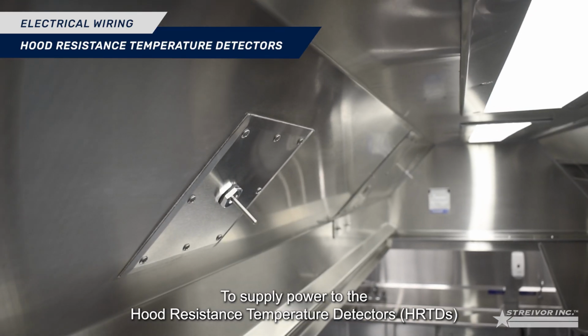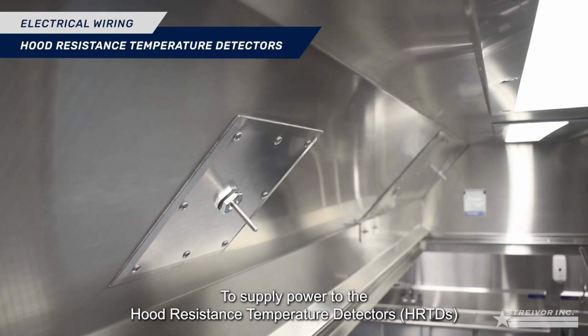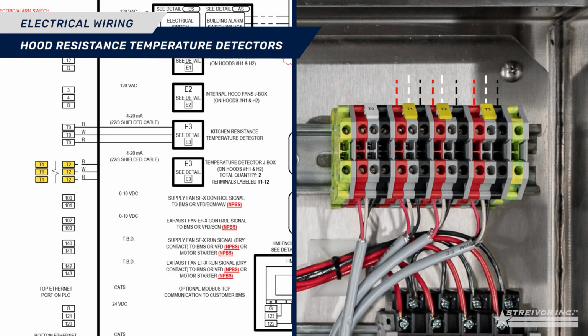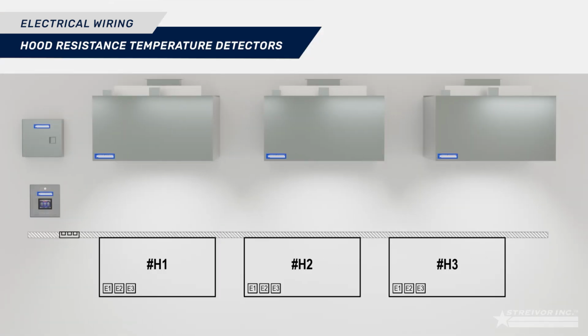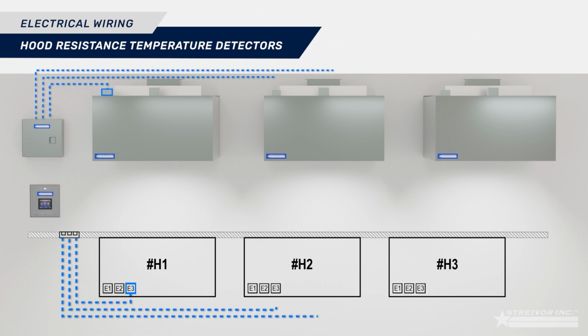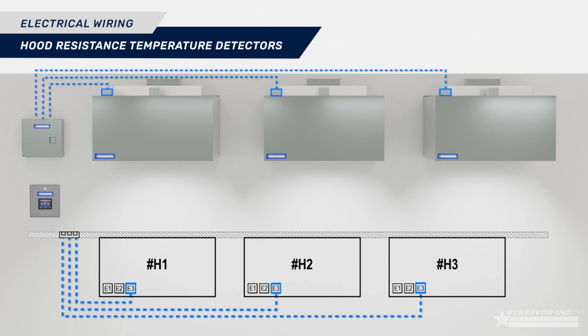To supply power to the hood resistance temperature detectors, HRTDs, connect the terminal blocks labeled T1, T2, etc. in the control panel to the junction box labeled E3 on the hood, using the UL-listed 22-gauge 3-strand shielded communication cable. Check the drawing for the specific quantity. If the control panel is controlling the HRTDs on multiple hoods, locate the E3 junction boxes for each additional hood and provide a dedicated run for each HRTD.